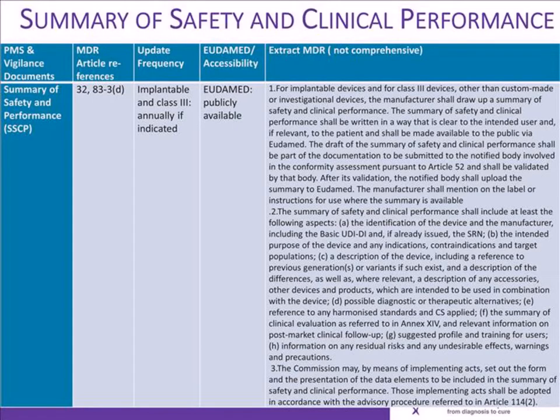Another one is a summary of safety and clinical performance. This is a document which will be made publicly available via EUDAMED. It's for class 2 and class 3. For class 3 and implants, it needs to be reviewed annually, which is certainly to be considered in terms of maintenance cost for workload.